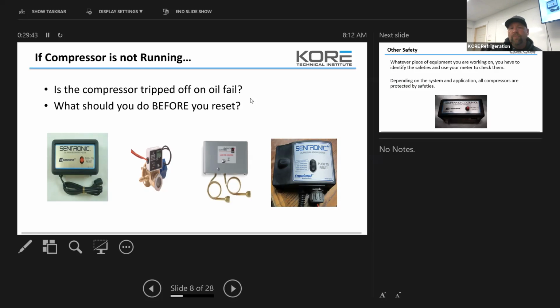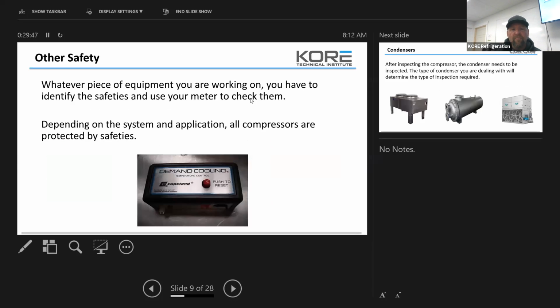So what should you do before you reset? Let's talk about what you should do before and what you do after. Whatever piece of equipment you are working on, you have to identify safeties and use your meter to check them. I don't want you to use the reset button as your check. Pull the covers off the controllers and use your meter to see what's open first. And then it's going to tell you what to do before you hit the magic button.